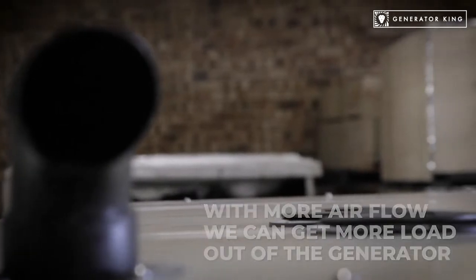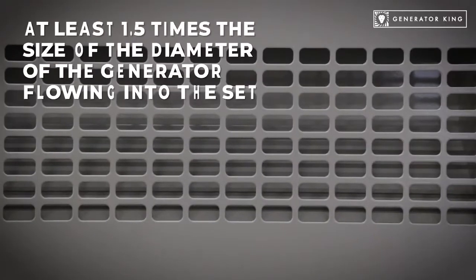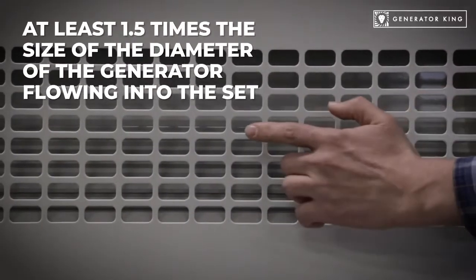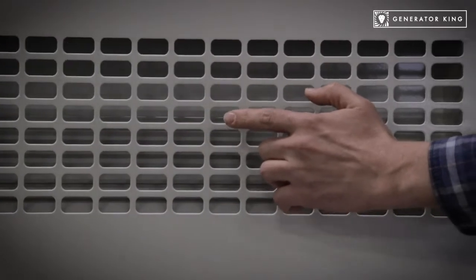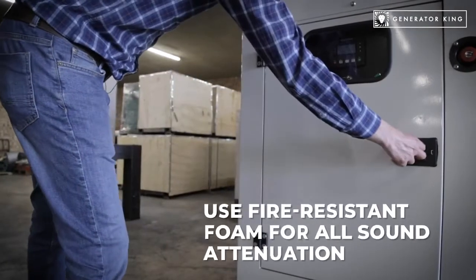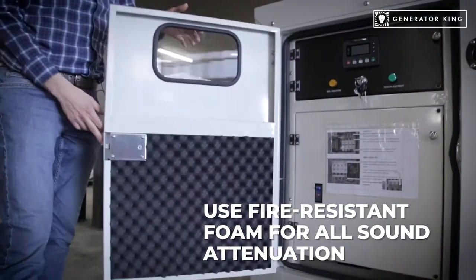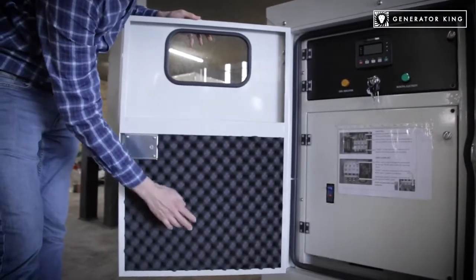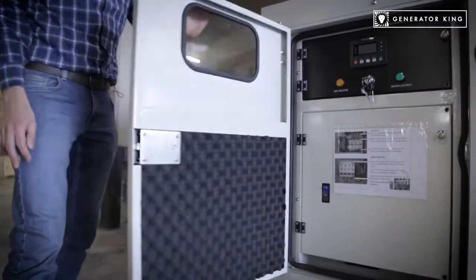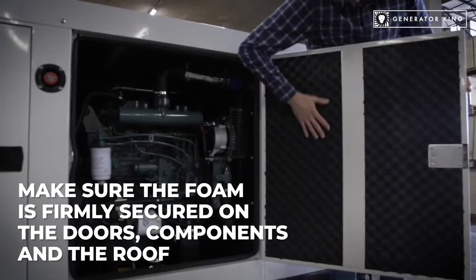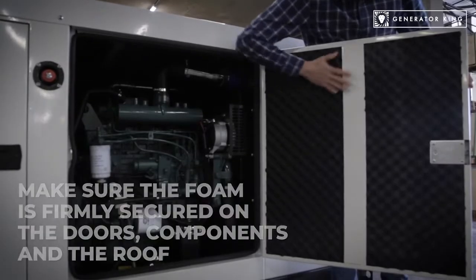As a rule of thumb, we want to have at least 1.5 times the size of the radiator diameter flowing into the set. Make sure the sound attenuation is made from fire-resistant foam. Some cheaper options have foam that can catch fire. Not a good idea on a generator. Also ensure that the foam is properly secured on the doors, components and the roof.